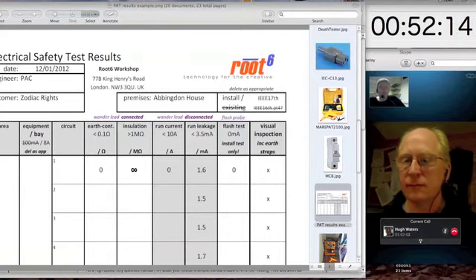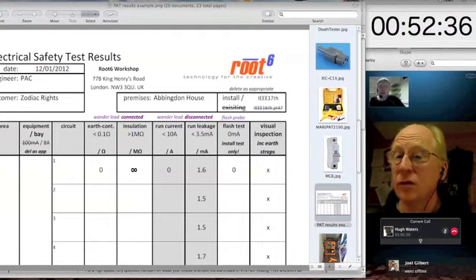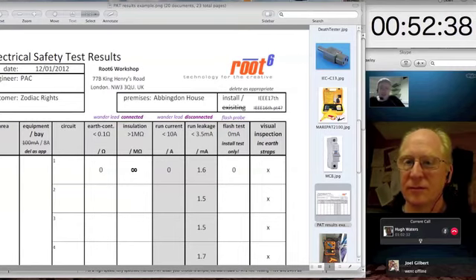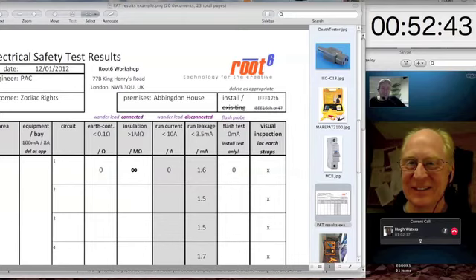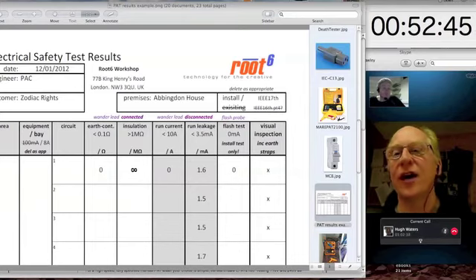So that's the earth continuity test, and if there's a switch on the machine, and if you're doing an earth continuity test on a particularly sensitive piece of equipment like a server or something like that, you can ramp the current at which it does the test down to 100 milliamps, because it's perfectly allowed within things like servers and musical equipment and things like that, the earth might be carried on a track on a PCB. That's allowed. Yes, of course. Yes, and if you're testing that at 8 amps, you run the risk of burning out the earth within the piece of equipment. And in fact, that happened to me. Such a thing could never happen.